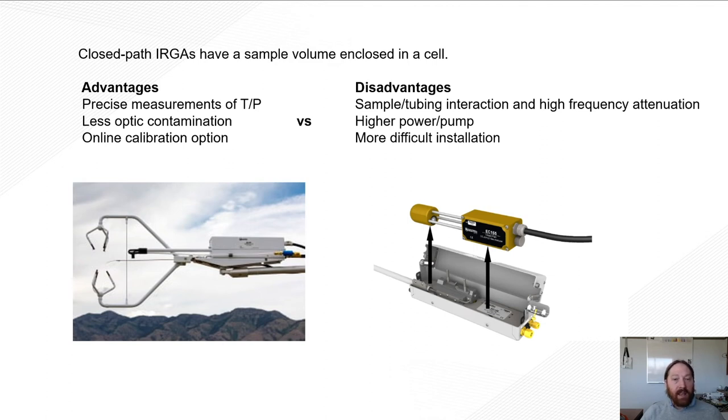Also, there's some online calibration options with our systems. So with our CPEC-310, our closed path system, you can add an optional tank of zero air and tank of CO2 span gas and use a valve module under datalogger control to perform an online calibration on an interval that you set.